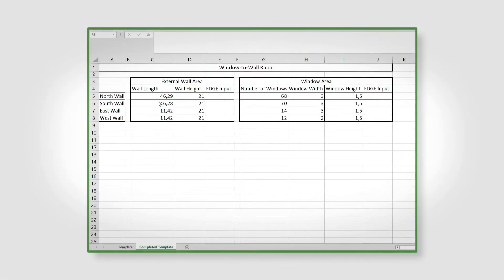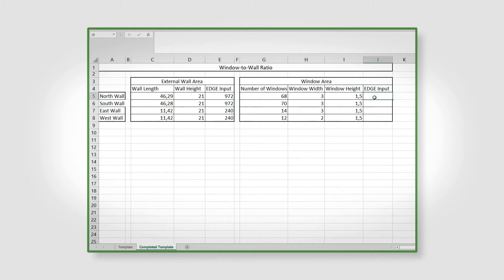To determine the WWR of your building, calculate the gross area of each exterior wall and the glazing area of that wall. Repeat this for each exterior wall of the building. Add the areas for the exterior walls that face the same orientation. For example, the areas for all exterior walls facing north must be added together. The same must then be done for the glazed areas in each orientation.